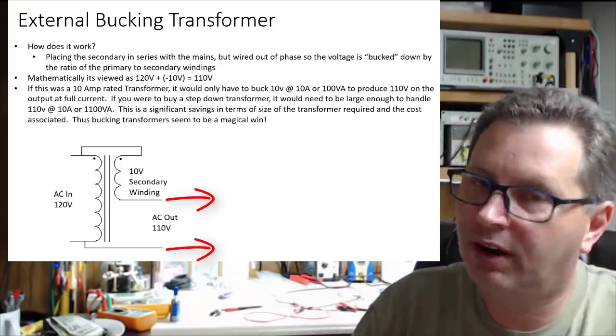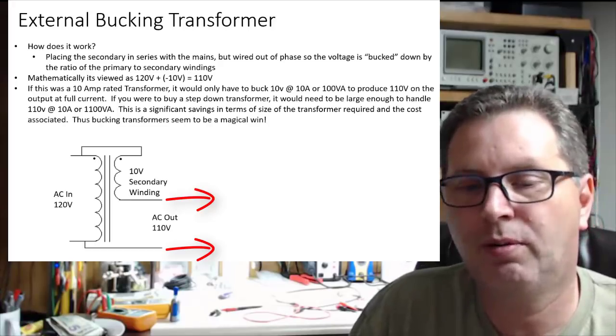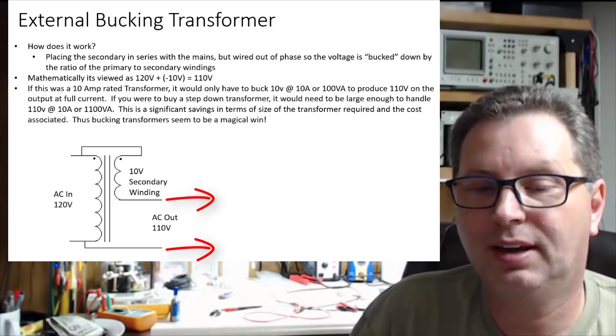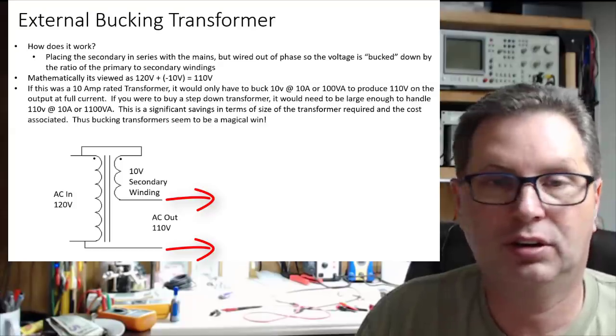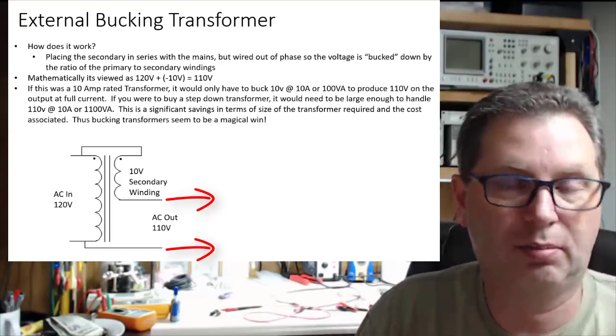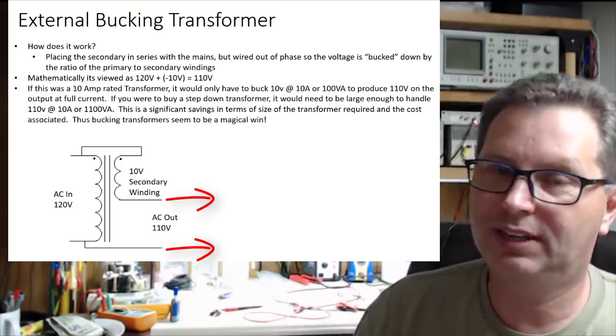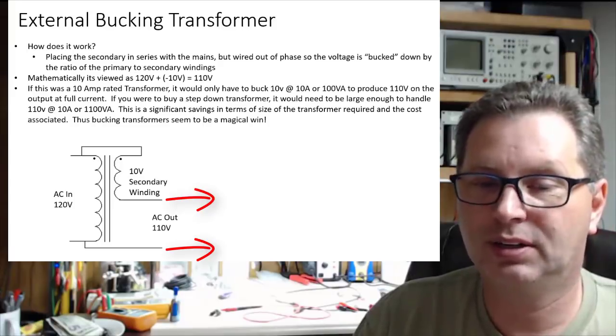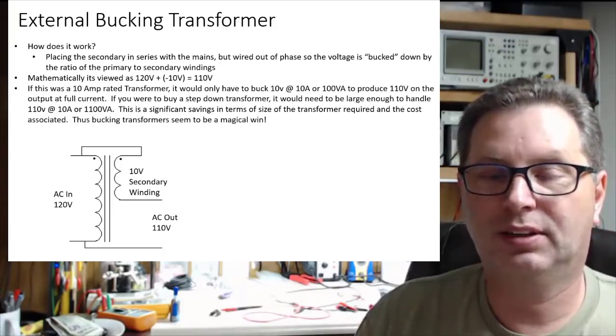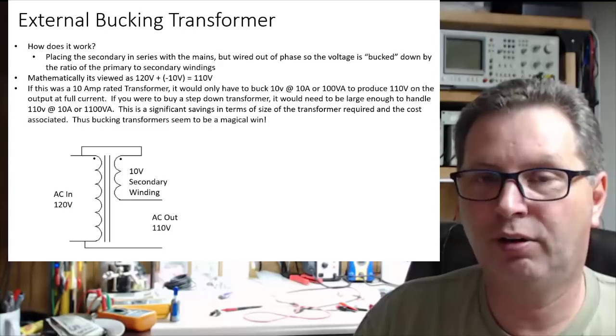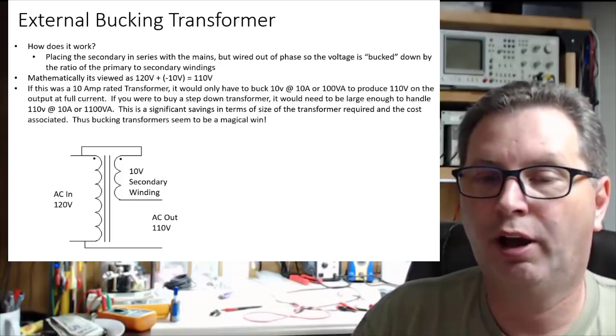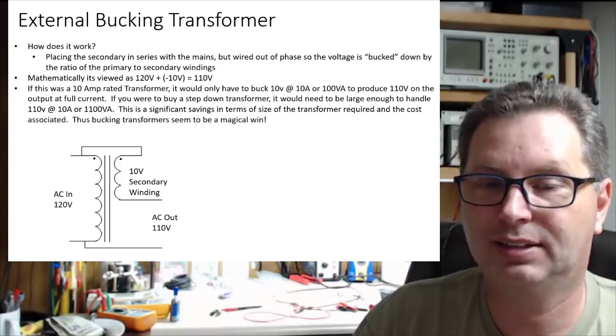It's somewhat a variation of an autotransformer. Just like the picture shows, you'll have to trust this a bit if you're not totally following the phasing: with 120 volts in, that 10 volts at the top bucks against the 120 volts, and you get 110 volts out on the AC.